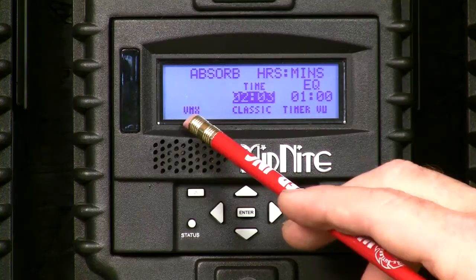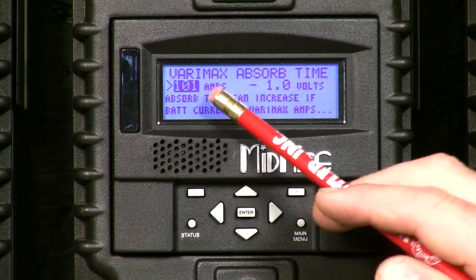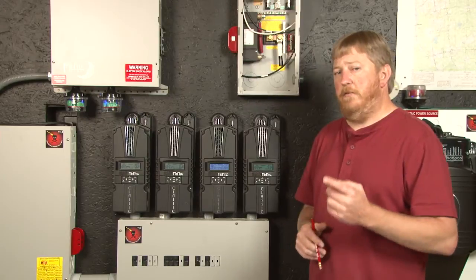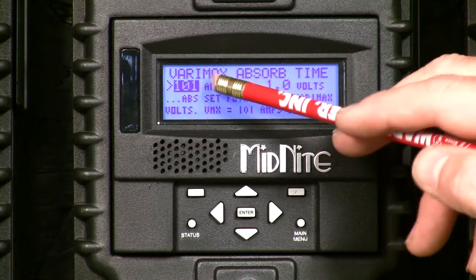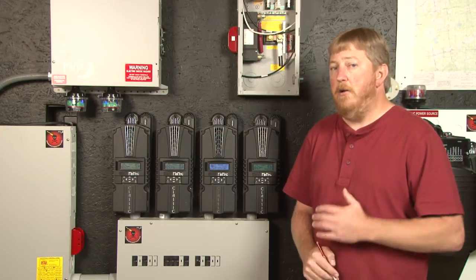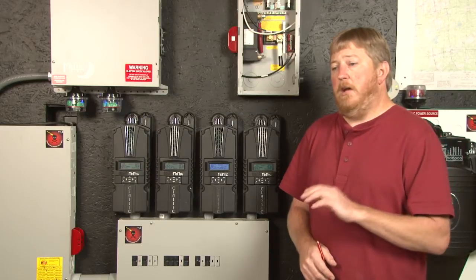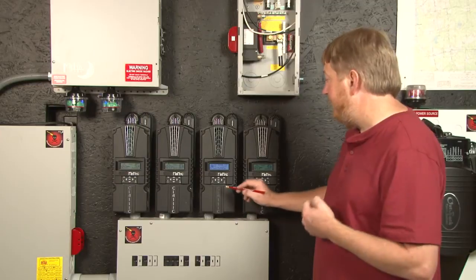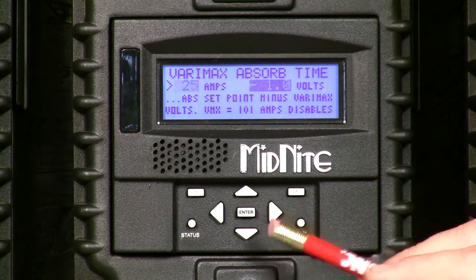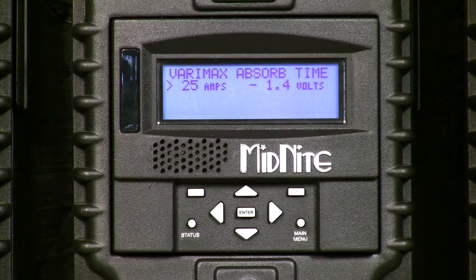Now I'll show you how to use VariMax. You'll see VMX for VariMax over here — we use the left soft key, the upper left button, and hit Enter. When you see 101 amps, that disables VariMax. If you do not want to use VariMax, just set it to 101 amps. In my case, I've found that about 25 amps is where I know if I'm pushing more than 25 amps into my batteries, they're not full no matter what the absorb timer says. I'm going to set mine for 25 amps and about 1.4 volts negative offset. I'll scroll down to 25, then use the right arrow to set the negative offset to 1.4, and hit Enter to save those parameters.